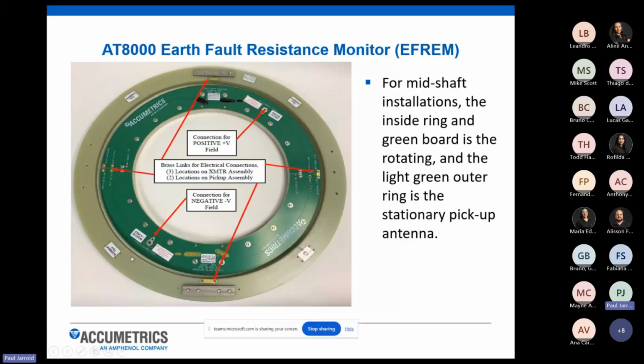And then we're bringing an induction power signal across from the stationary world to the rotor to power the electronics that are mounted inside of this transmitter. So the transmitter is a high-strength steel collar that's machine specific to each customer's diameter size of their exciter shaft. And it houses an electronic module in one half of the collar, and then the other half has a weighted module for balance. So all of these systems, we've done dynamic testing, balances in spin pit facilities, as well as static testing. So all of these systems are designed to be balanced and not interfere with any issues on the generator, on the exciter rotor.